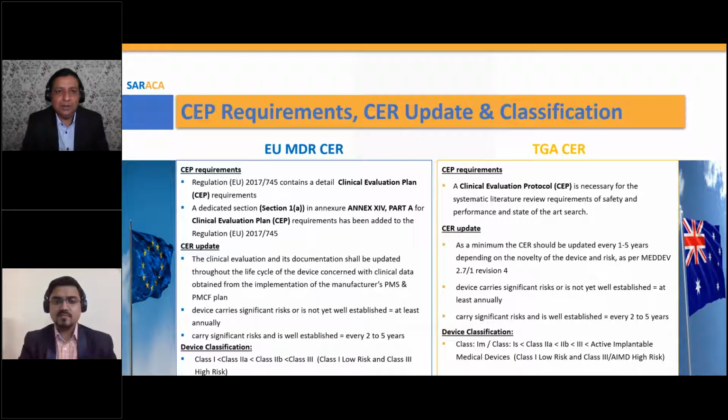As soon as you get your field updates, you're getting complaints, you are going out in the market doing PMCF, you're getting certain feedback, which triggers that you will have to update your DFMEA, PFMEA, or software FMEA. And as soon as you do those updates, you need to come back and see if anything has changed in your CER or CEP. So the best assessment is with you.